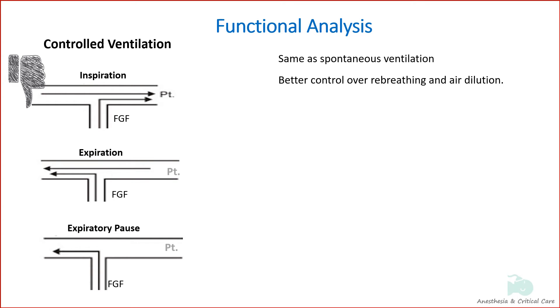During expiration, the occlusion is released whereby the expired gas from the patient as well as the fresh gas fills the reservoir tube and are vented out.